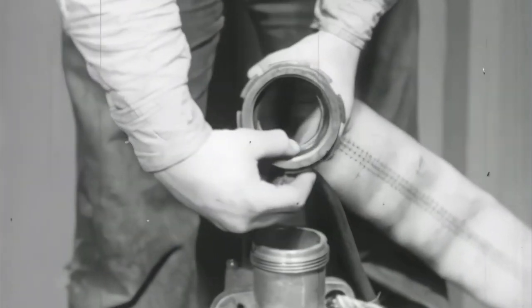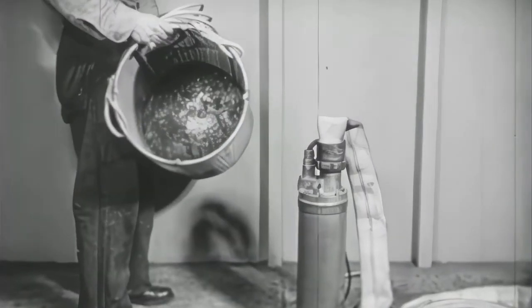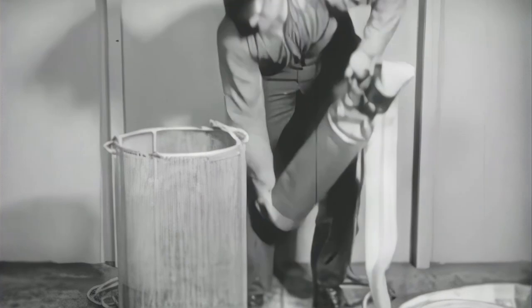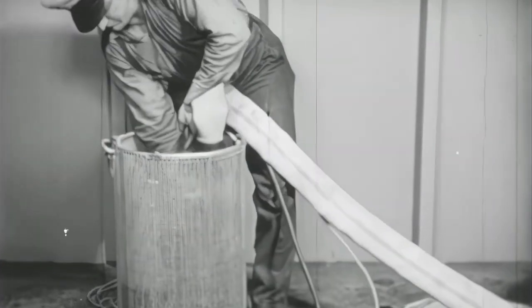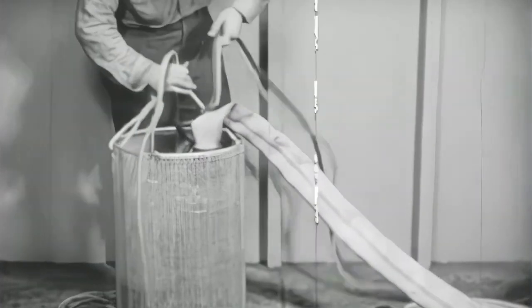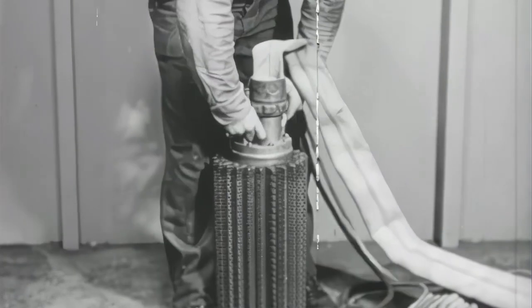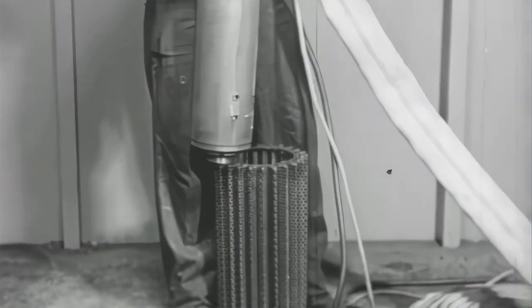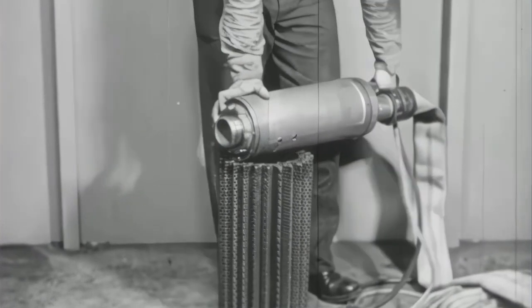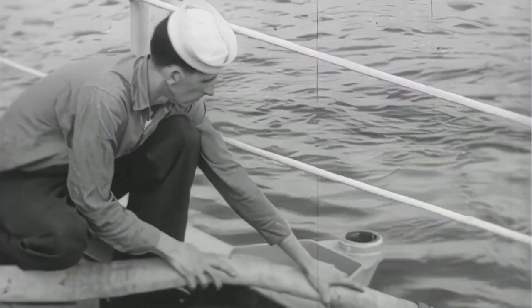Before connecting the hose line, be sure there is a gasket in the fitting. To avoid clogging the pump strainer, a wire strainer basket provided with a bale or lowering line should be made up for use with each pump using quarter-inch screen. The basket should be small enough to pass through a scuttle; the strainer bale should be lashed to the discharge hose, or the two lowering lines can be married together. The most efficient type of strainer is a fluted design of perforated metal. At a discharge head of 50 feet, the pump will deliver 140 gallons per minute.